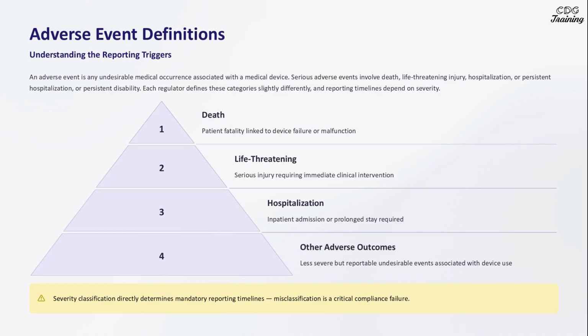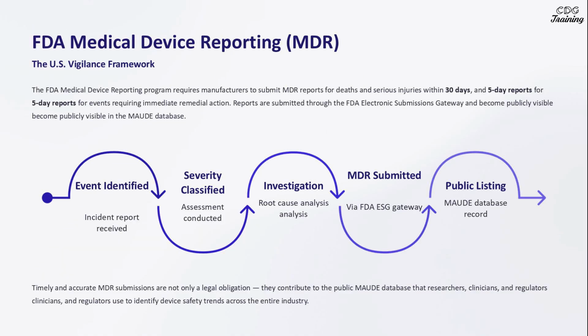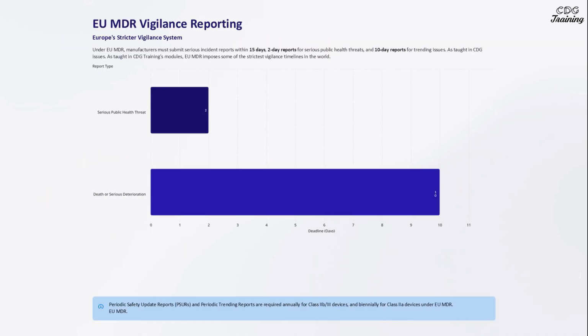Adverse events are categorized by severity, from death to other outcomes. Proper classification and reporting are crucial for compliance and patient safety. The FDA's Medical Device Reporting Program requires timely submission of reports for adverse events, contributing to a public database that enhances industry-wide safety. Under EU MDR, manufacturers must adhere to strict timelines for reporting incidents, ensuring rapid response to potential public health threats.